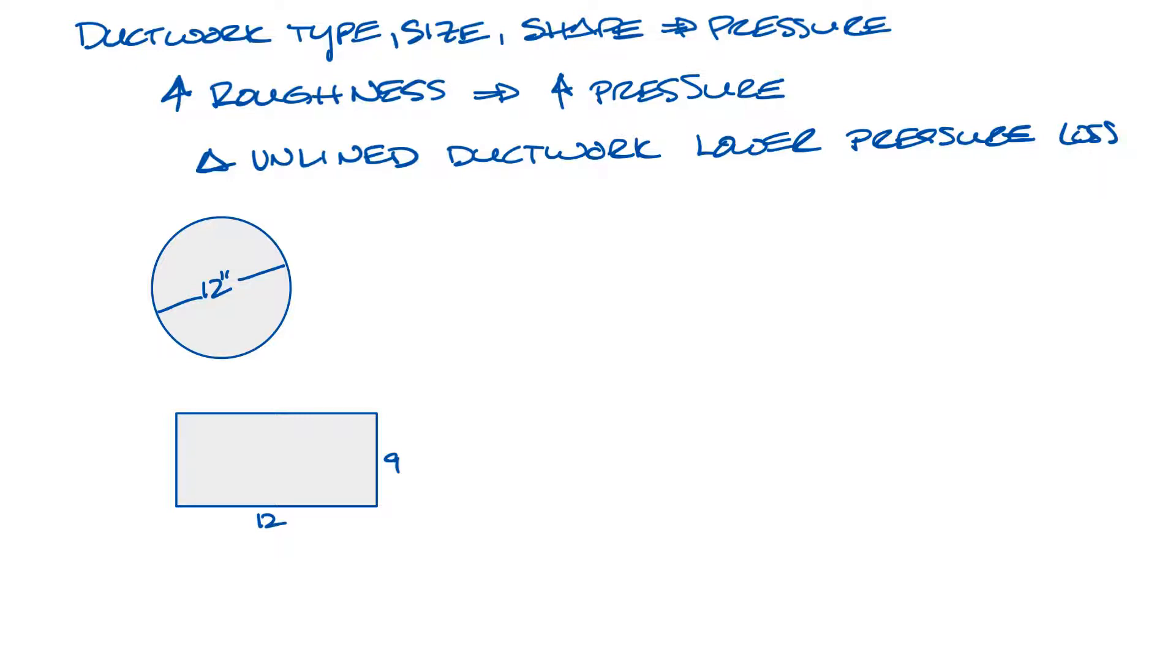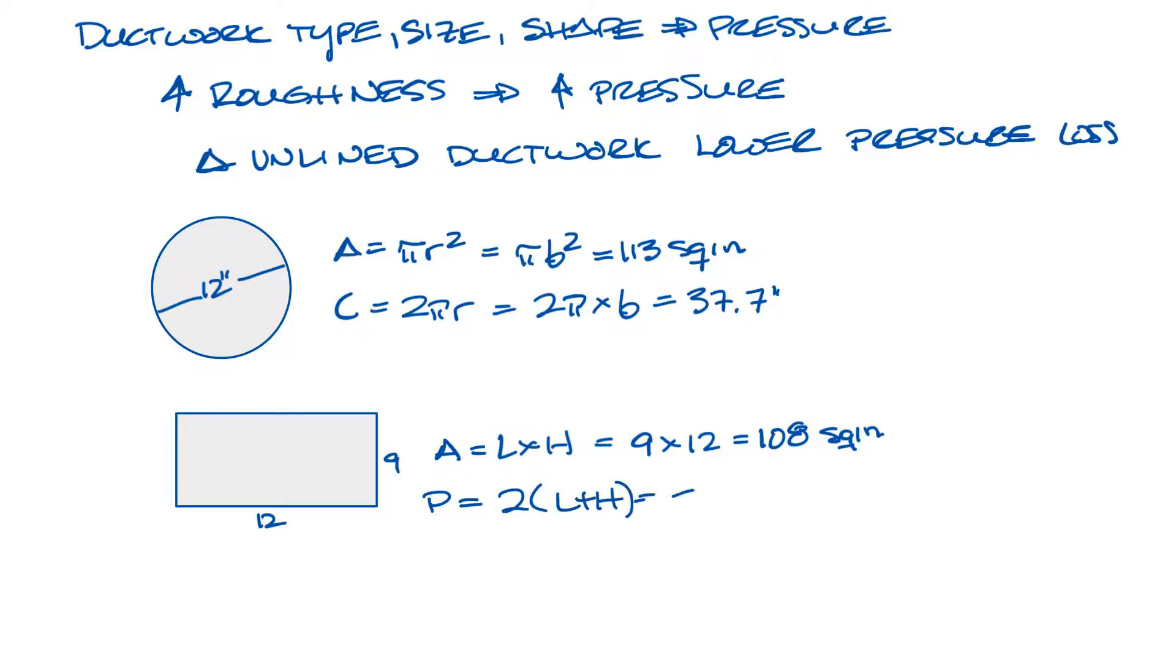So for the circle, the area is pi r squared, and r equals 6, which comes out to 113 square inches. And for the rectangle, it's length times height, which comes to 108 square inches. So pretty close. But now if we look at the surface area that the airflow will have contact to, that's 2 pi r for the circle, and that equals 37.7 inches. And for the rectangle, it's going to be 2 times length plus height, and that will equal about 42 inches. So the rectangular actually had a smaller area for the airflow to pass through, but more surface area for more friction.